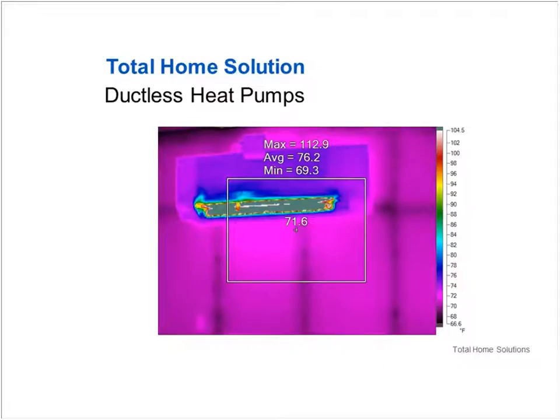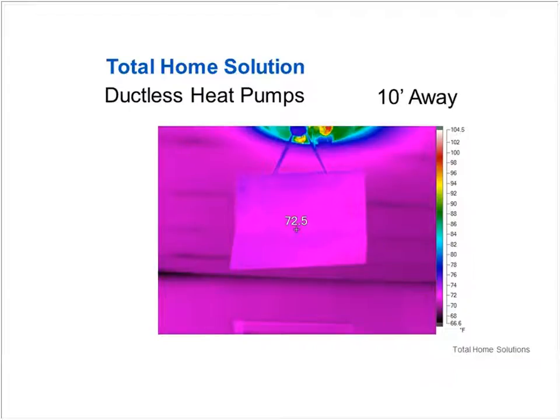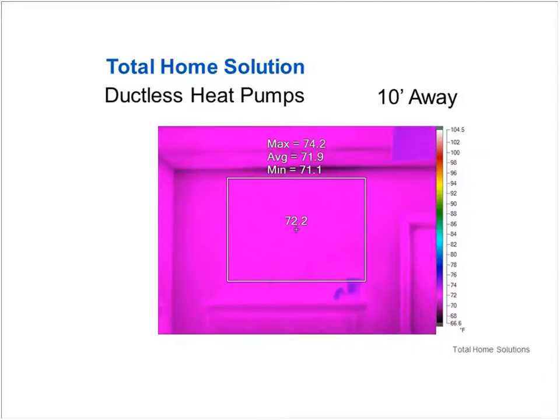But the way the ductless heat pump works is it heats the mass. So here's a register head right here, and you can see the max output is around 112, 113 degrees. And literally you can see the stud walls behind that and the nails and so forth. But when they run at consistent temperature, this is 10 feet away, so it's 72.5 degrees, 10 feet away. At 20 feet, it's 72.2 degrees. So we lose 0.3 of a degree in 20 feet. And what happens is it winds up heating the mass and keeping the mass at temperature. And as long as the mass is at temperature, the room will be at temperature.